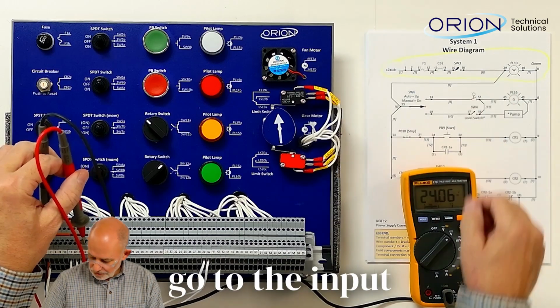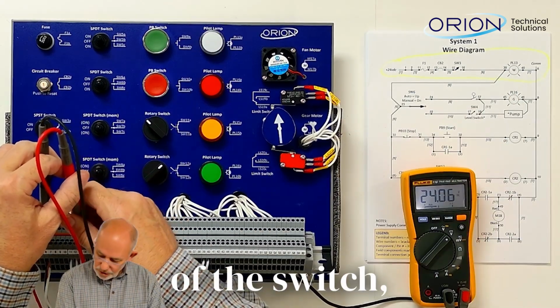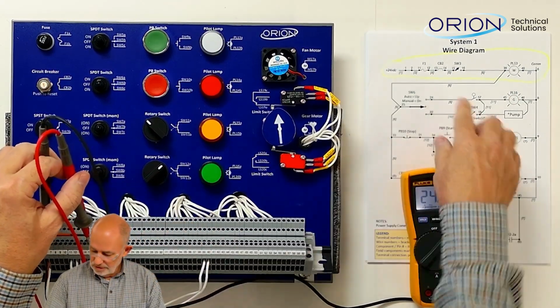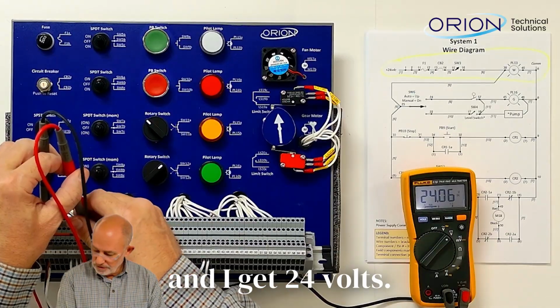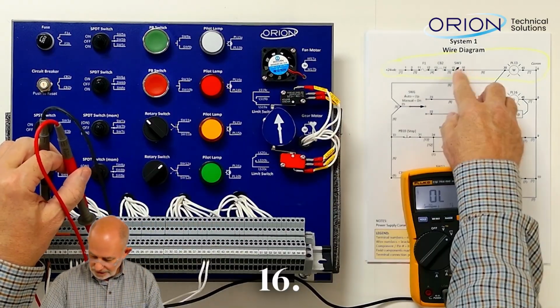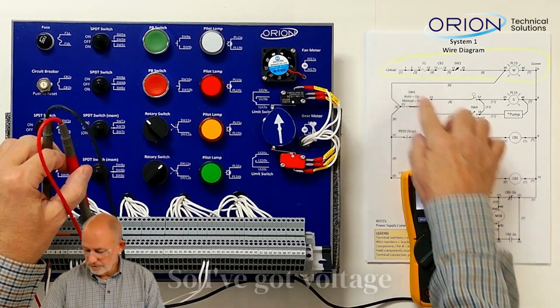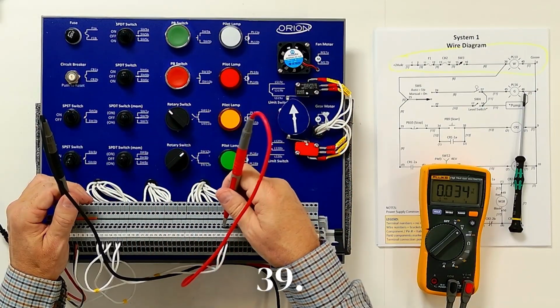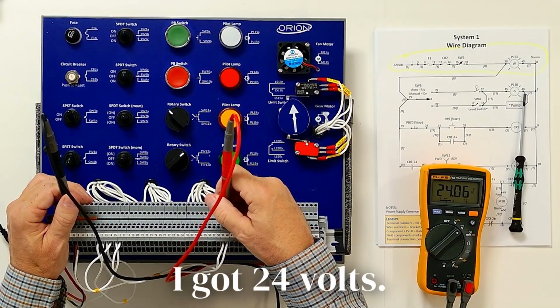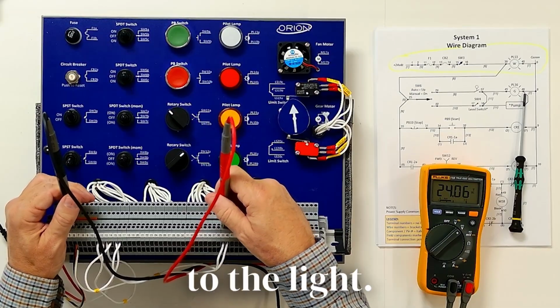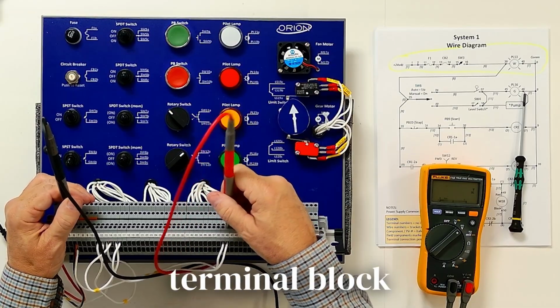Now I'm going to go to the input of the switch, which is terminal block 15, and I get 24 volts. I'm going to go to 16, 24 volts. So I've got voltage all the way to here. And now I go to terminal block 39. At terminal block 39, I got 24 volts. There's power to the light. So now I'm going to check terminal block 40.